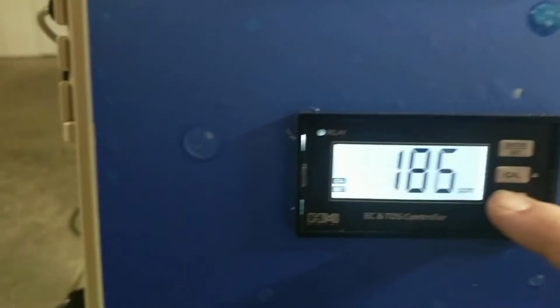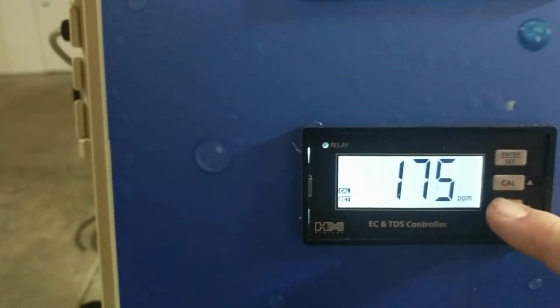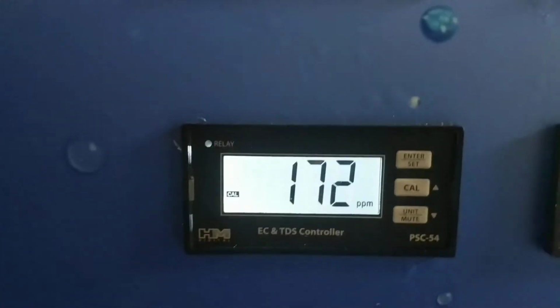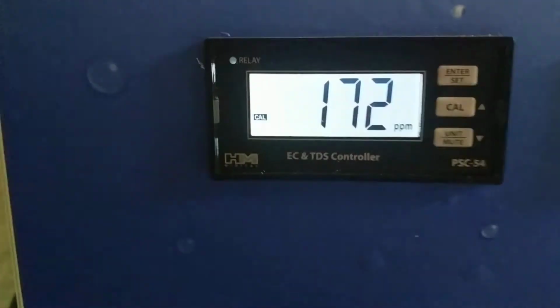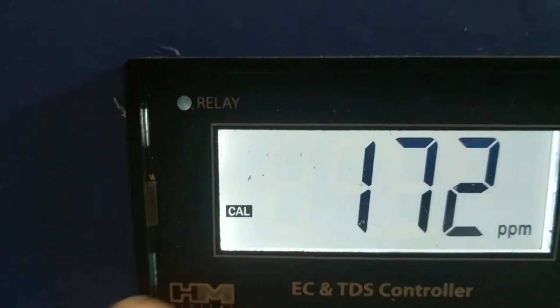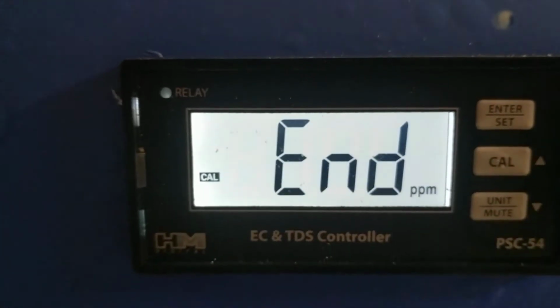Okay, go down to where you want it to be. I want it to be right at 172. I'm going to go ahead and hit Enter, and that's going to do the rest. So if that cal light is blinking, that's what you want. It now is calibrated at 172.